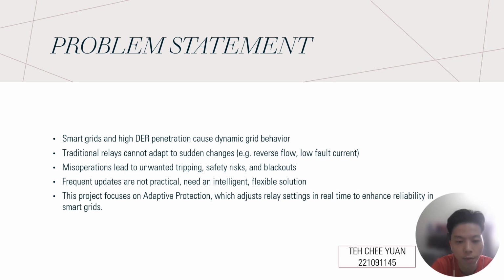They are set with fixed parameters and they expect predictable conditions. So when something unusual happens like a reverse current or low fault current, they may misoperate. That means unnecessary tripping, blackouts, and even safety risks. To fix this, frequent relay updates would be needed, but that's just not practical in real time. It would take too long and require too much manual work.